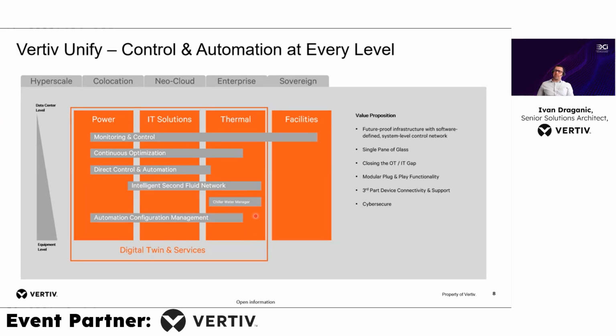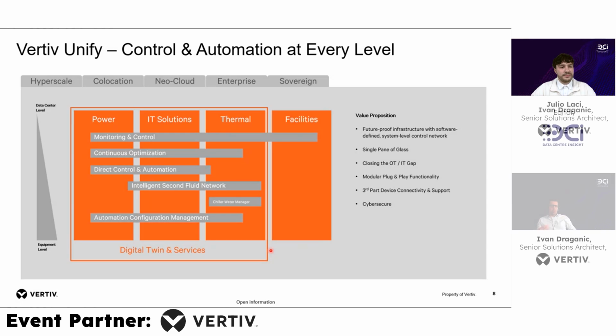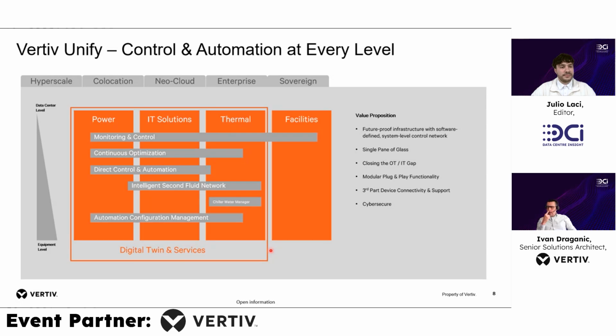So the thermal systems - I've mentioned the liquid cooling system and the valves we have there. All the systems are monitored. We have the control, and we can stop the leakage based on the leak detection system. We know where the leakage is happening, and we have automated solenoid valves that can, at the operator's choice, just snap a finger and stop the flow through that branch.